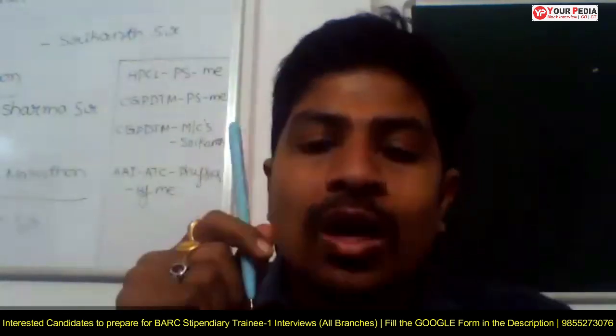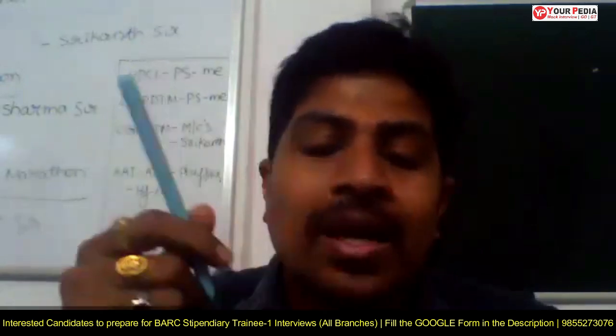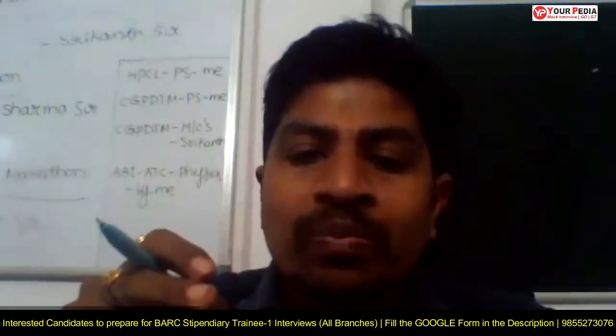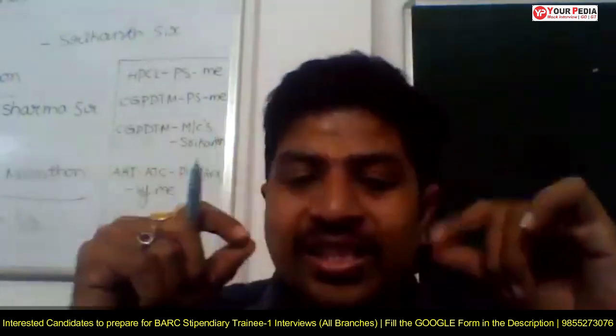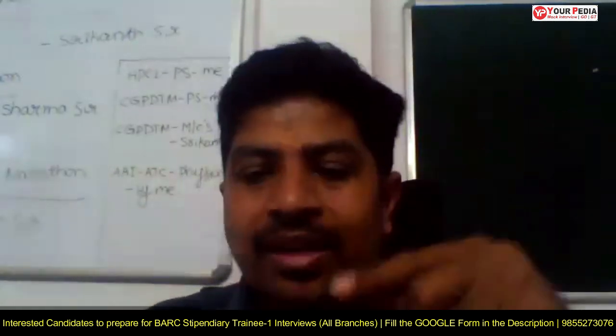If it is unbalanced, there will be a resultant amount of flux. That flux is going to cut with the communication lines. Radio interference is going to happen. That's why, to not have this unbalanced effect because of unsymmetrical configuration, we are going to do the positional exchange of the conductors at regular equal space intervals. It is called transposition of transmission lines.